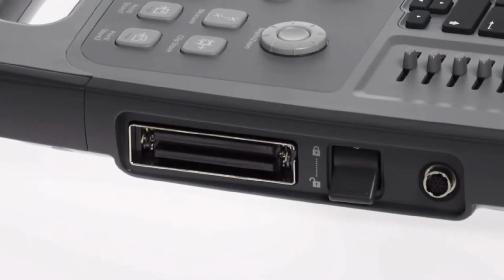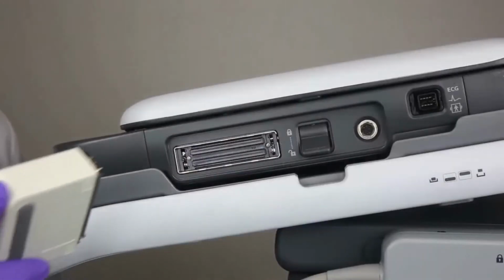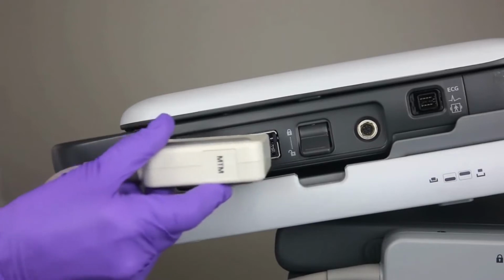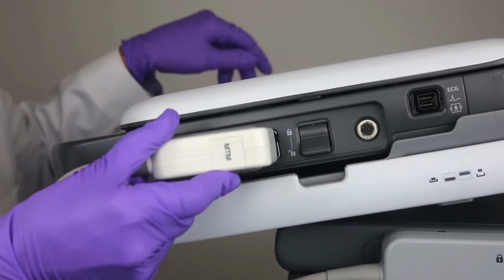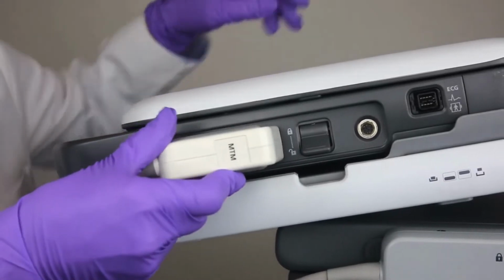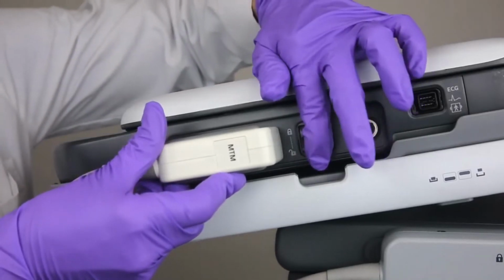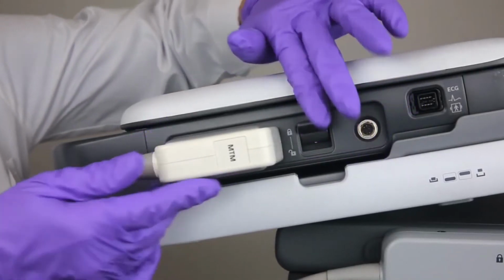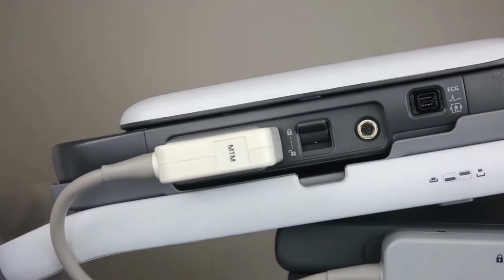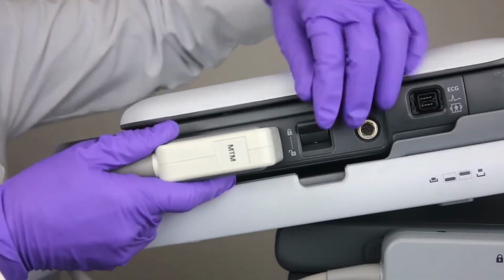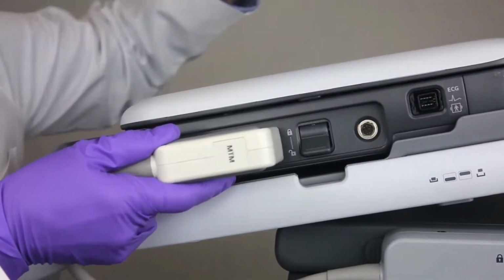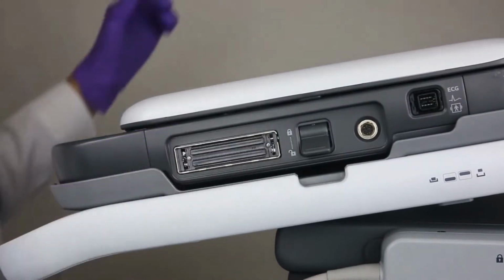To connect a transducer, ensure that the transducer lock is in the unlocked or down position. Align the transducer with the connector towards the front of the Acuson P500 system as shown. Insert the transducer and push in firmly. Switch to the lock position to lock the transducer. To remove a transducer, move the lock to the down position and pull the transducer away from the system.